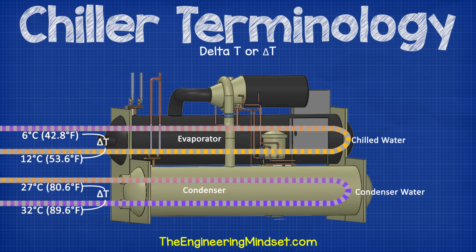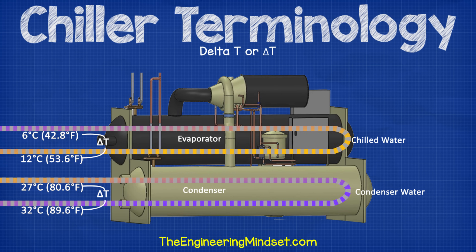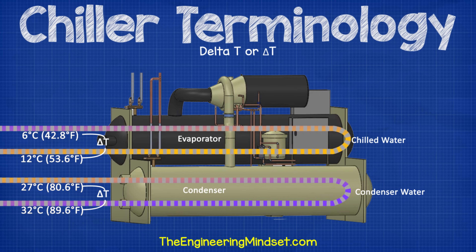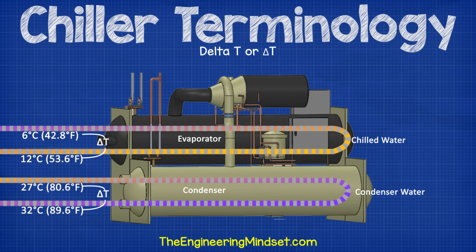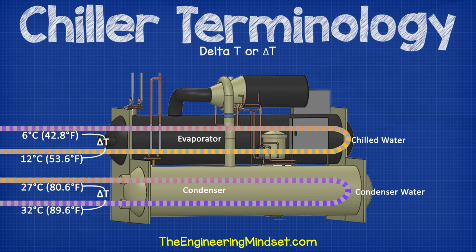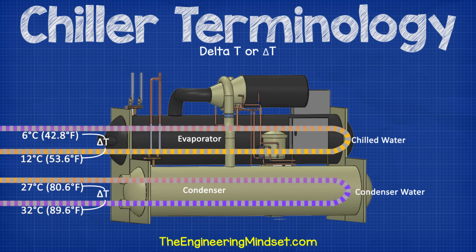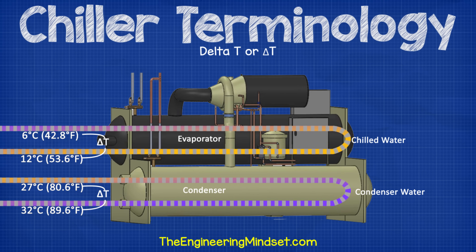Delta T. This refers to the temperature difference between the flow and return temperatures of either the chilled or condenser water. A typical temperature difference between the chilled water flow and return would be 6°C, but this can vary. A high delta T means the chiller is working hard and the efficiency should also be high, whereas a low delta T means that the chiller is likely operating inefficiently and there are likely design issues with the cooling system causing this.